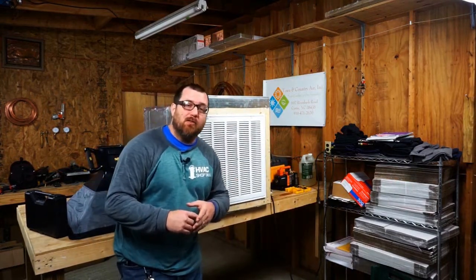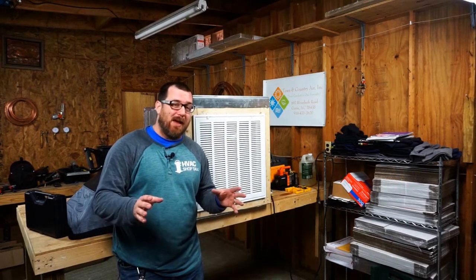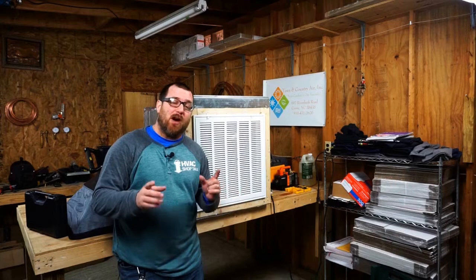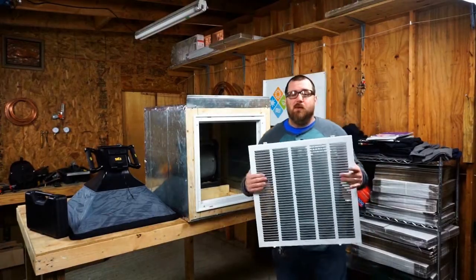I spoke to a very high-up, important person at CPS, Mr. Scott Madden. He let me know that there are some alterations we can make to try to even the test up. He also let me know that the Easy Flow hood from CPS does have compensation for higher static pressure. So we're going to do the test one more time, except we're going to make one important change. We're going to remove this grill.